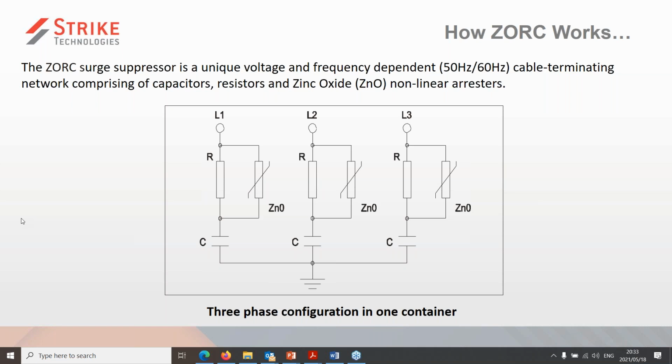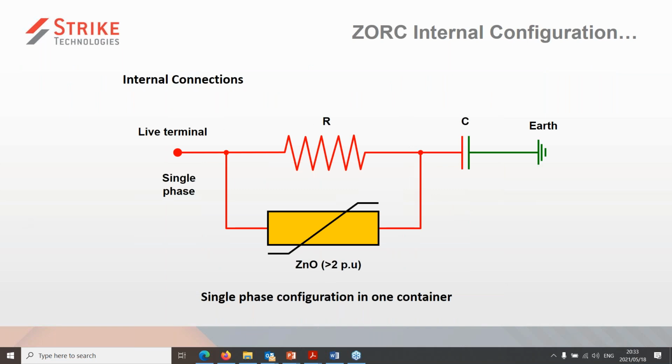If we simplify this a little bit and we look at the single phase, or take one of the phases of the single phase application, we have the capacitor, the resistor, and the zinc oxide block in the configuration as you see it there.